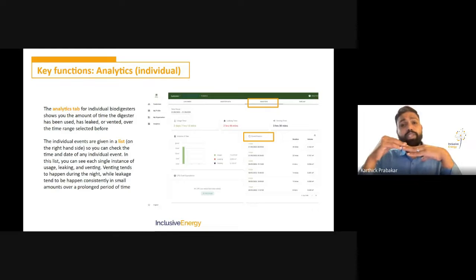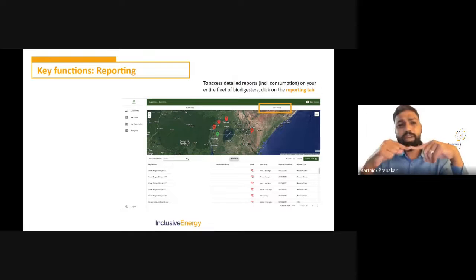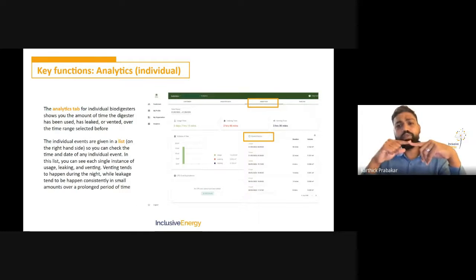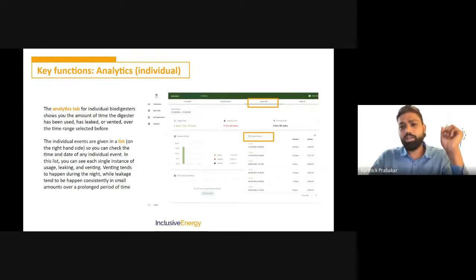Analytics can also be seen on an individual level when you have thousands of digesters in the field and want to analyze a small sample. You can select the time period, select the digesters, and click on analytics to get the analytics for those digesters alone. It also gives you events of venting, events of leaking, and usage on an individual digester level, with the number of hours and the volume used or leaked. On the right, you see an events history, which gives you the time at which it was leaking and the usage also, so you can cross-check when you see an event recorded.